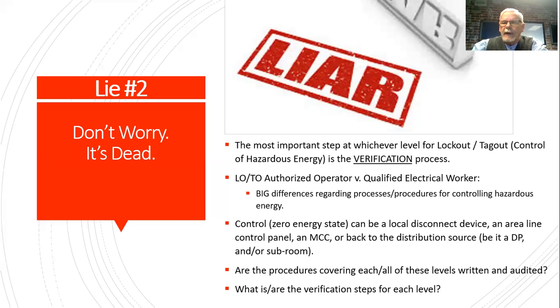Qualified electrical workers, on the other hand, are a step up based on knowledge, experience, be they trade certified, whichever. They are not going to simply throw a switch, put a lock on it, hit a button, and then go from there. Their verification is going to involve testing. They're going to use their meters. They're going to take their meter and they're going to read it. Once again, testing is touching. So if it's a 480 feed, if it's a 480 disconnect, they have to be in the appropriate PPE when they open it and test it to verify that, yes, in fact, it's dead.